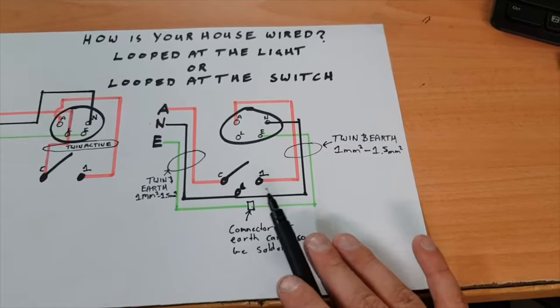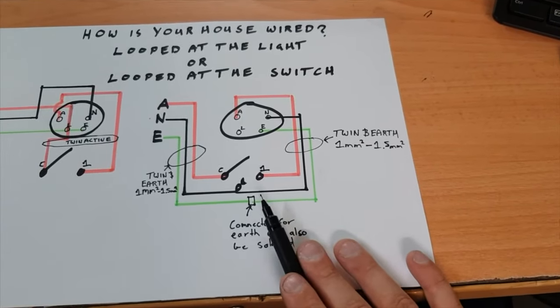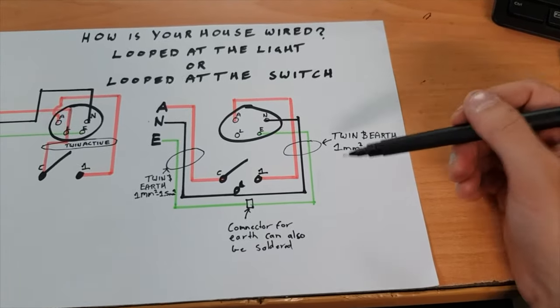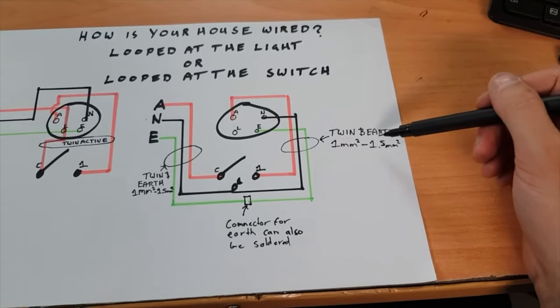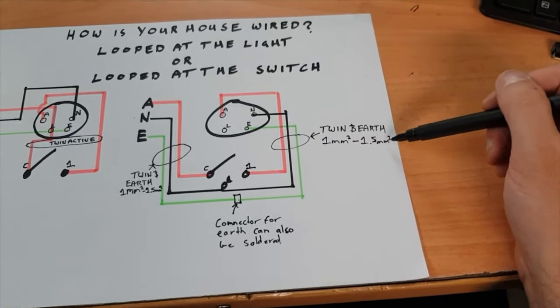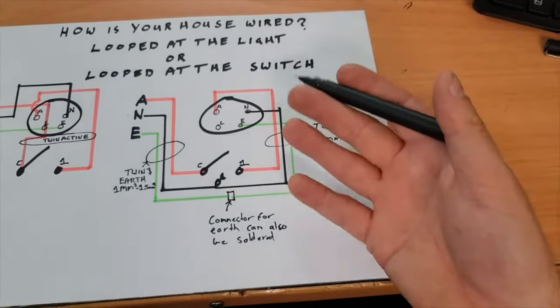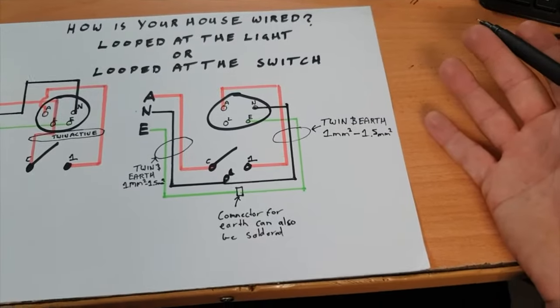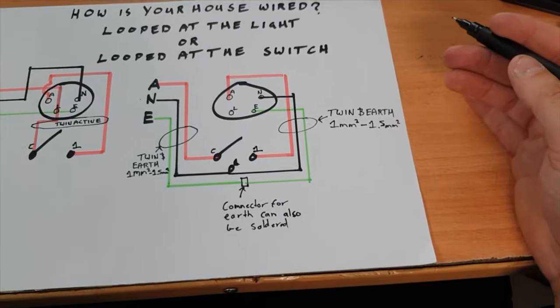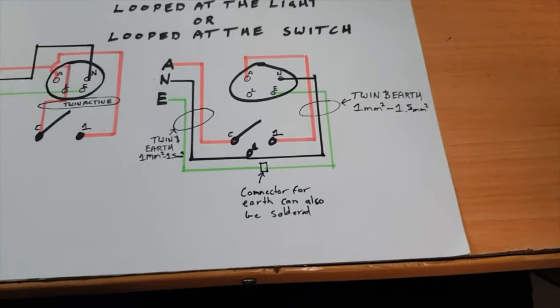Now from generally what happens is in say the new houses and pretty much any added additions, this cable here that goes from your switch to the light is normally a twin and earth cable. So in your house you'll either have a one mil or 1.5 mil cable. This type of cable even comes in 2.5 and 4 mil and 6 mil and so on, but it starts to become a bit of overkill for just a light. Your power points are wired in 2.5.